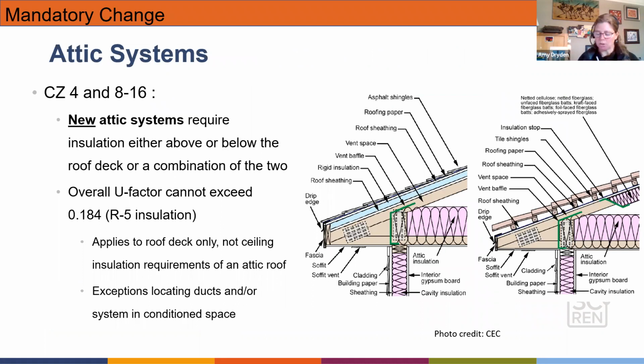So let's get into a couple of the different elements of mandatory changes. Here on attic systems, it's now mandatory for new attic systems in climate zones 4 and 8 through 16 to require insulation either above or below the roof deck, or you can do a combination. That is in addition to what you may have at the ceiling level, above the conditioned floor area. Yep, go ahead.